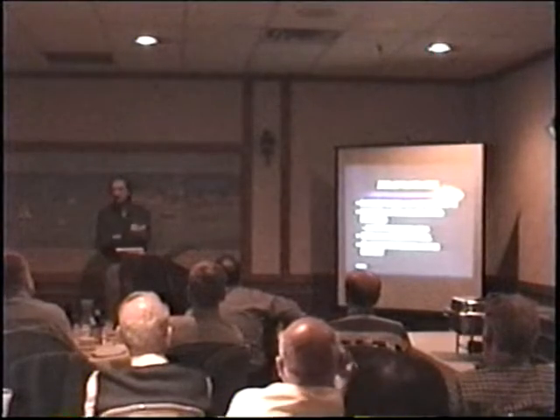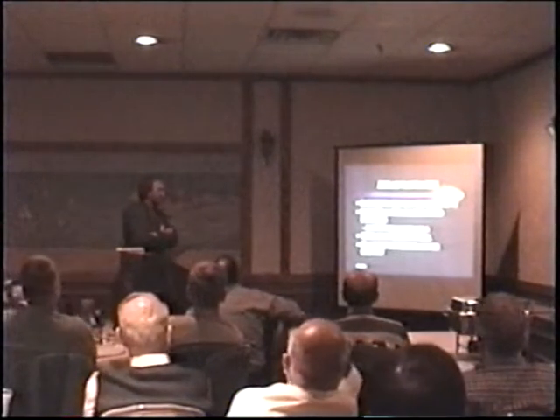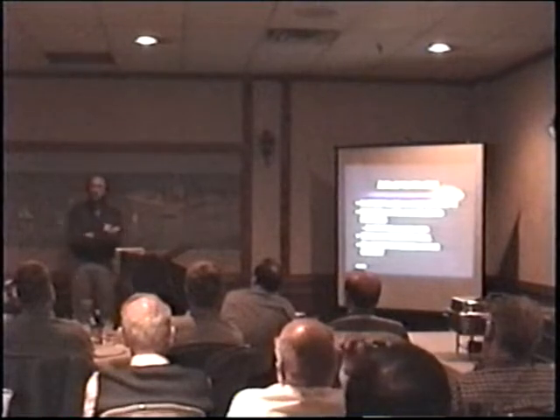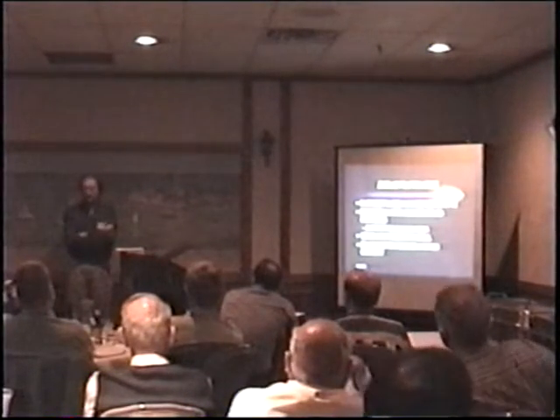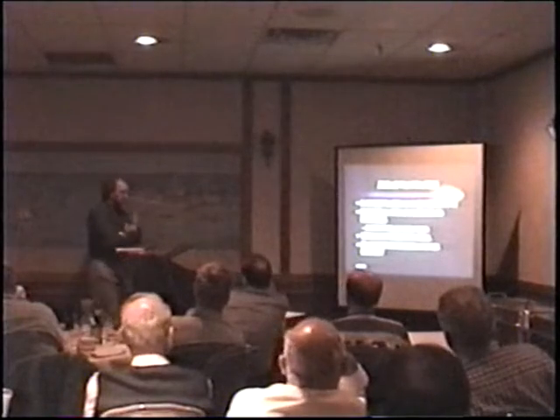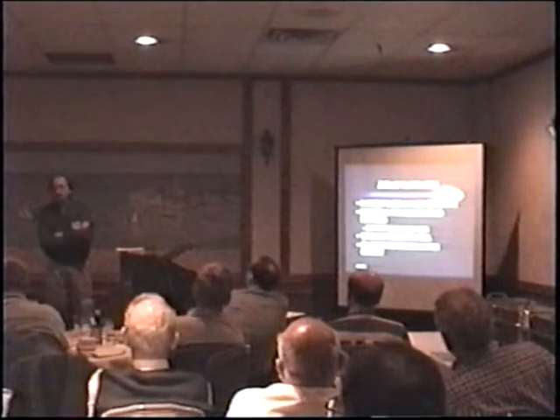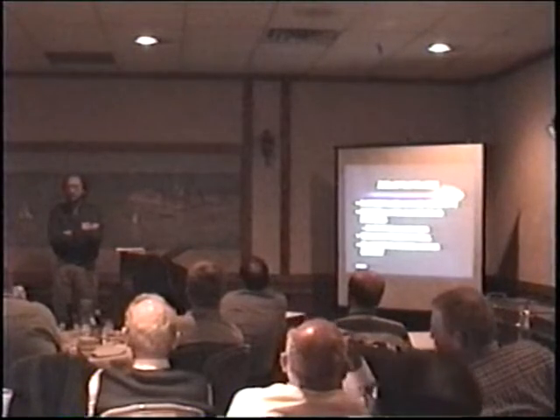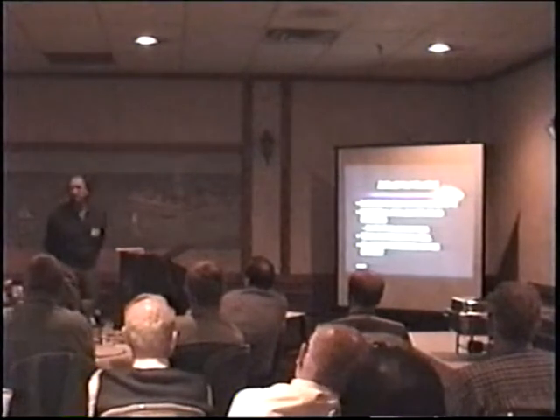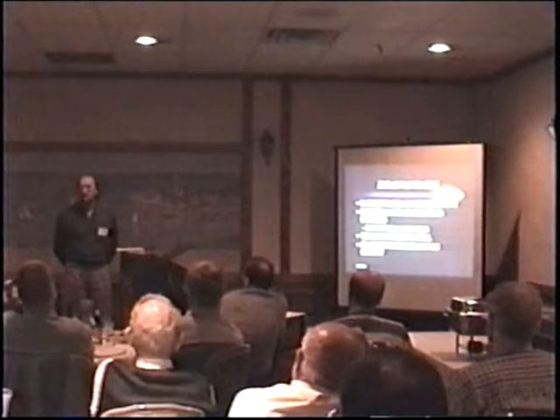Disadvantages of bladder tanks: bigger tanks, when you get up over 2,500 gallons, 3,000, 4,000 gallons, they get pretty big and expensive. They're not exactly ideal for closed-head systems because your ratio proportioners have to have a minimum flow before they're going to proportion fully. And with the wide use of the alcohol-resistant concentrates, that raises the low flow up even more because it's a more viscous product. There's a couple companies that have come out with low flow proportioners that are a variation of the old standard ratio controller like we have. It's a different design and allows you to proportion at a much lower flow. So you could use a 6-inch controller, which normally would have a flow range of maybe 500 to 3,000 gallons. These new variations will allow you to get down to maybe one sprinkler.